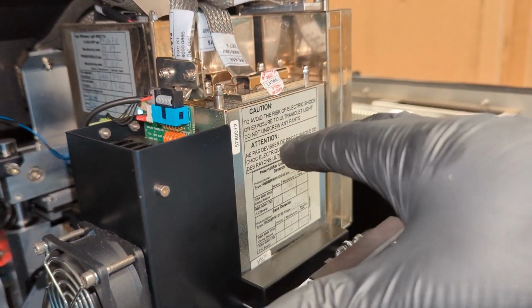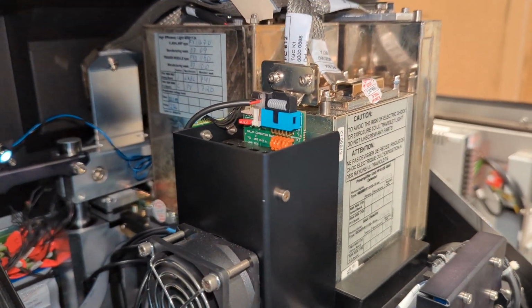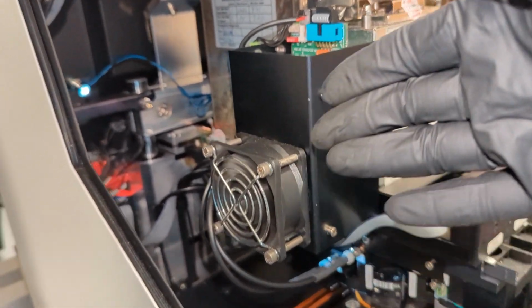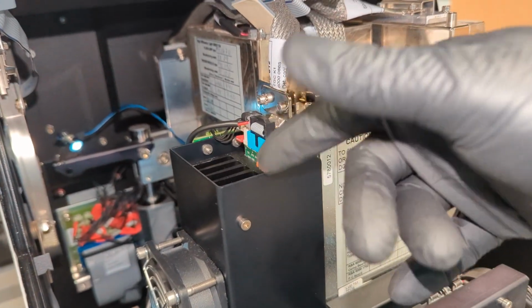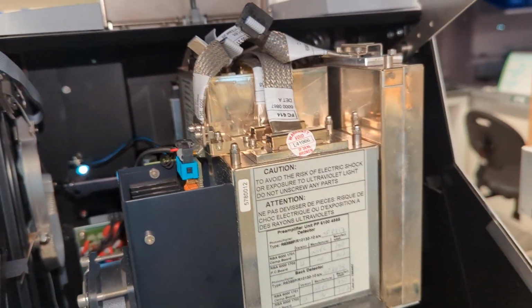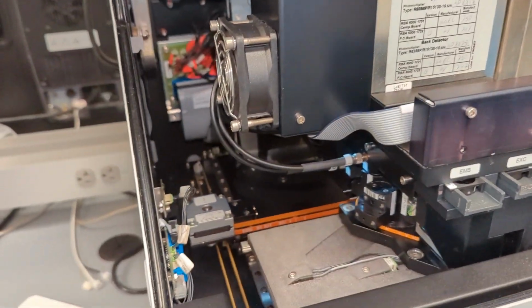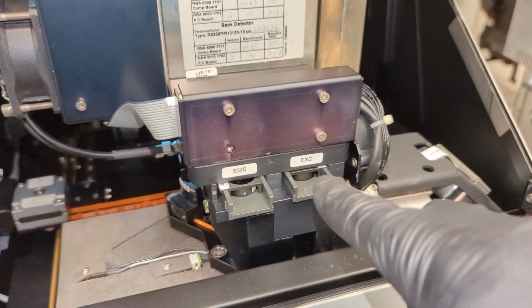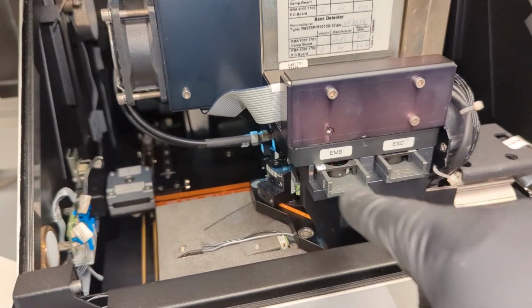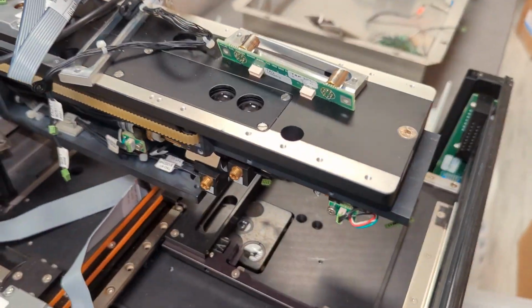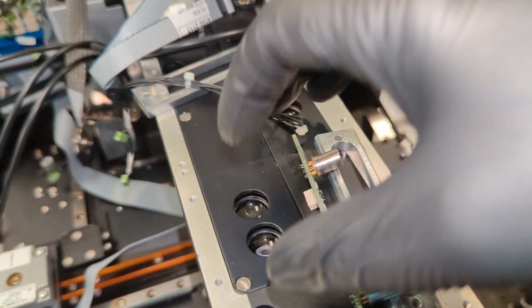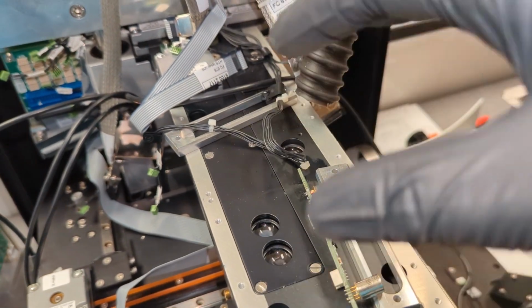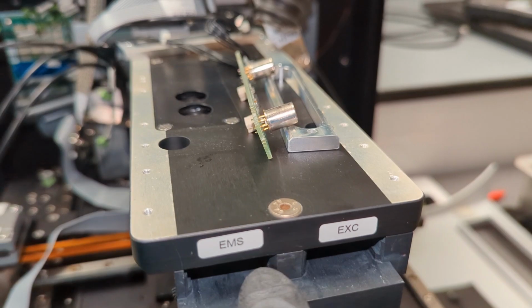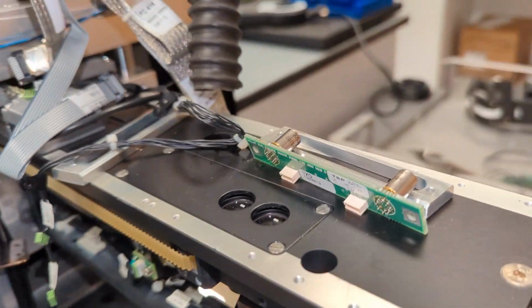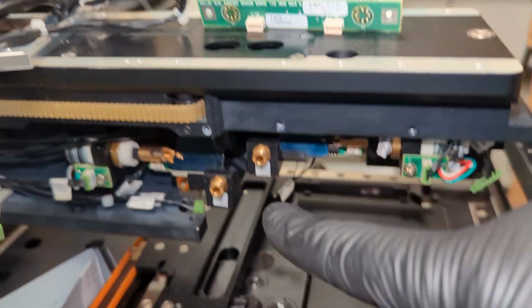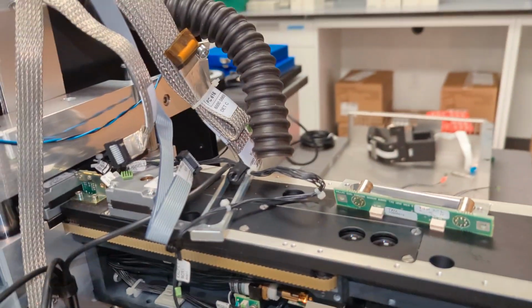We're going to open one of these up in a second. I have one of them open so that we can take a closer look at some of the internals there. This is your detector cooler, so this is just a fan with a Peltier element. You've got this big heat sink there for the Peltier element, and that's all that's doing, just making sure the detectors are kept cool so that they're not overheating. And then of course, just like with the excitation light, these emission filters are also in that path. And so again, you can see that pretty clearly here. These are the lenses for where your PMTs would sit, right above the emission filter rail, and so that's also in between the PMTs and the emission light selectors. So it's pretty cool.